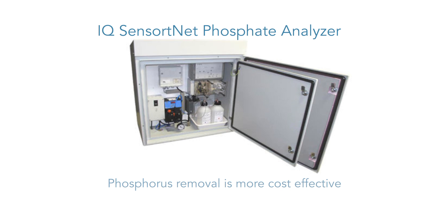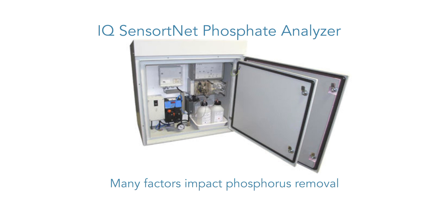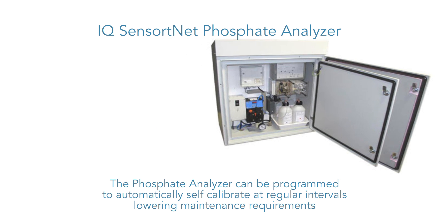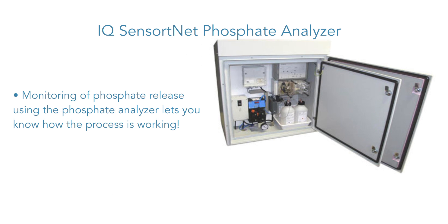Enhanced biological phosphorus removal is more cost-effective for meeting limits less than 0.5 milligrams per liter. Cycling between anaerobic and anoxic zones creates conditions for bacteria to release and then take up excess phosphate. The amount taken up is more than the amount released because bacteria store extra phosphorus. When those bacteria are removed from the system through routine wasting, phosphorus is also removed. Monitoring of phosphate release using the phosphate analyzer lets you know how the process is working.